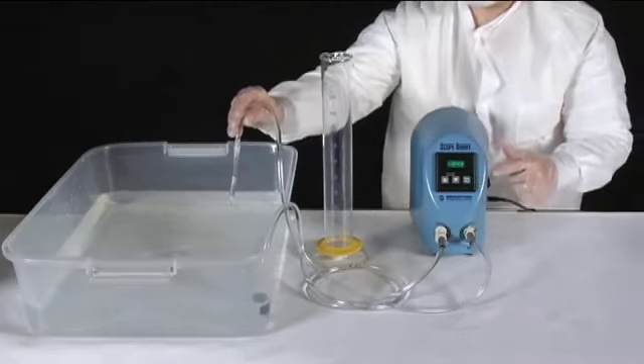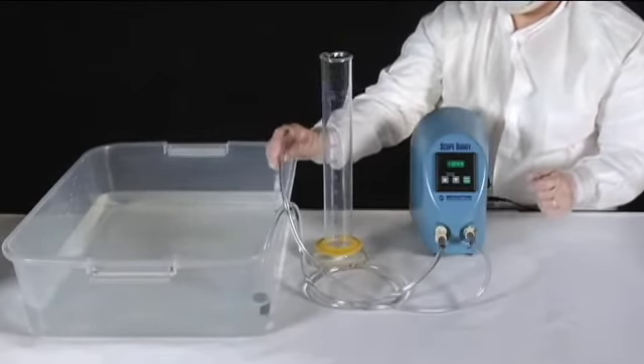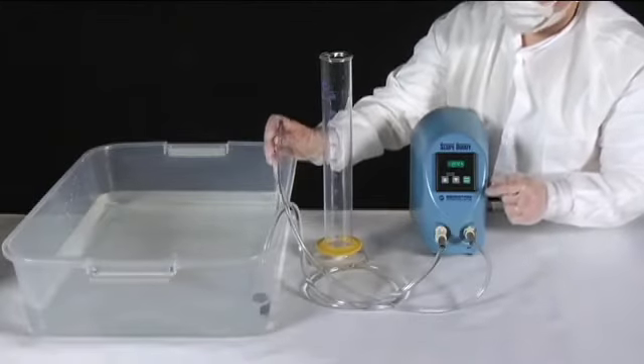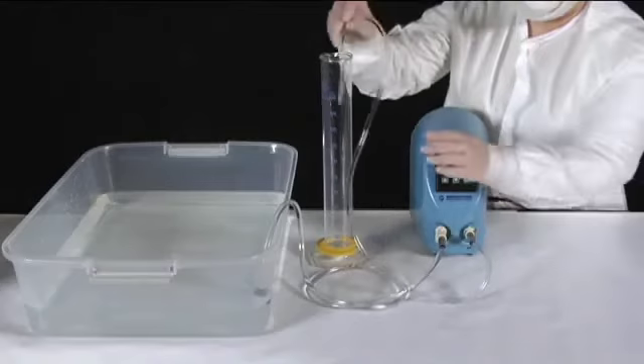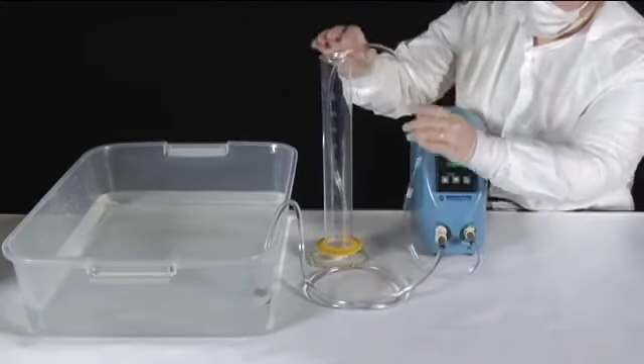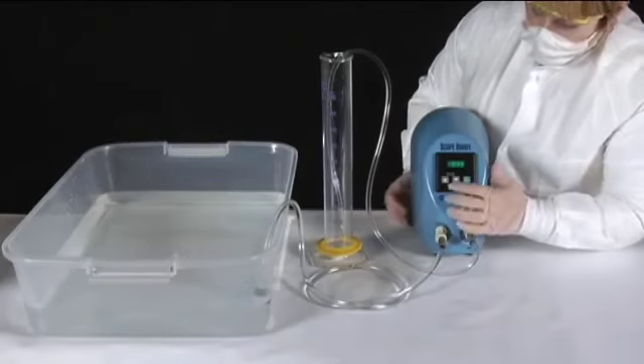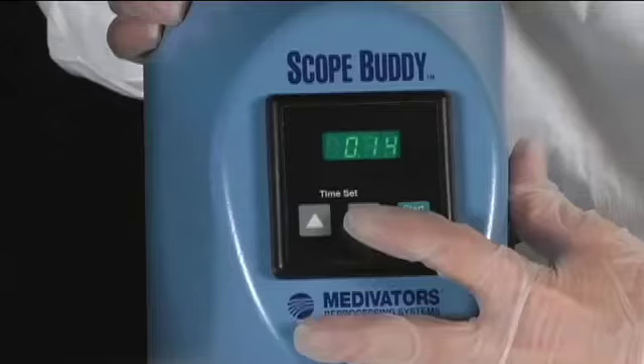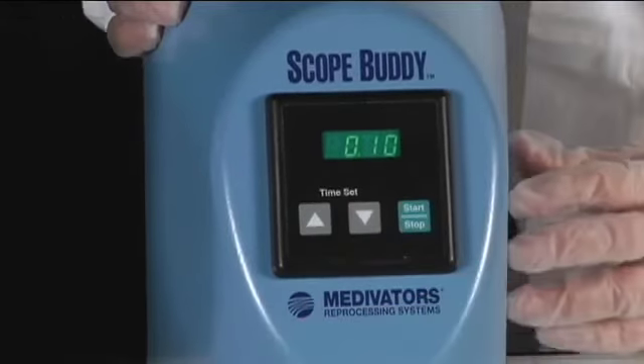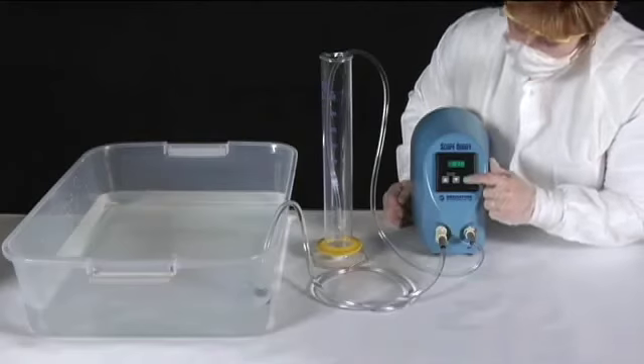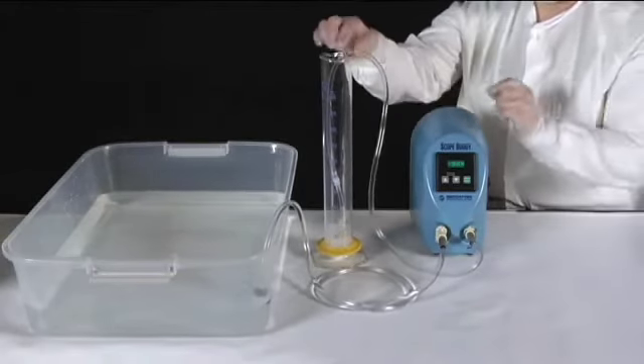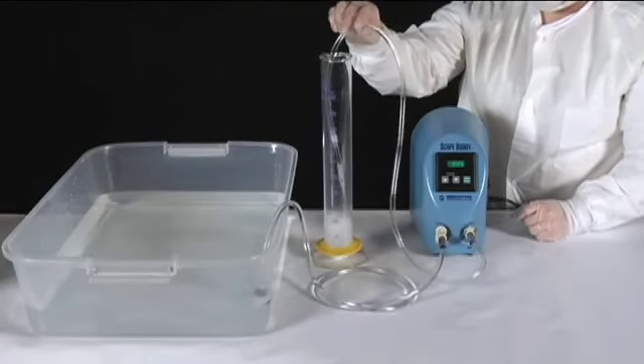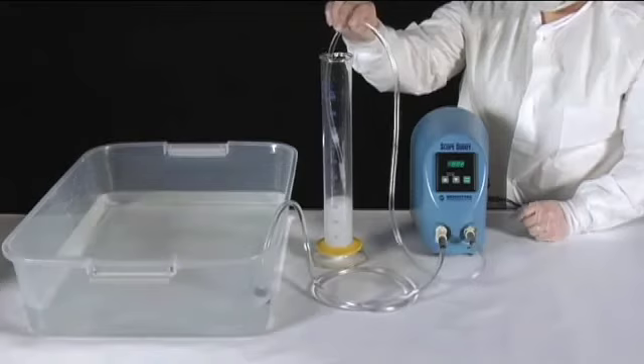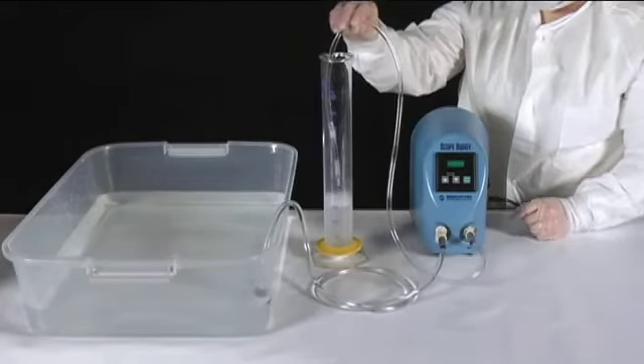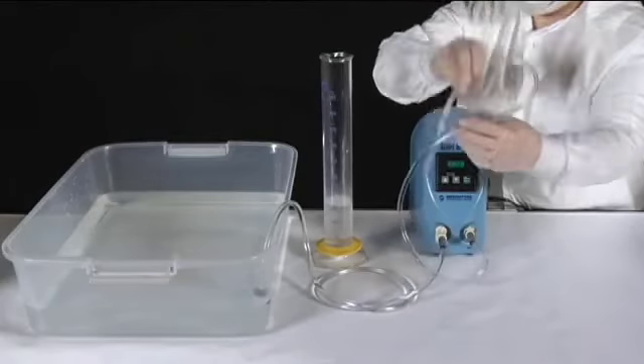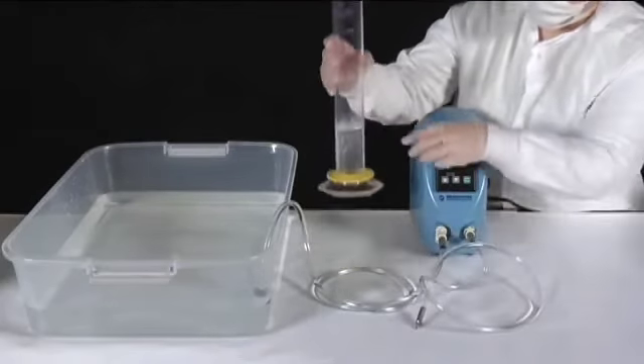To perform the flow verification test, place the open end of the pre-primed flow verification tube into a graduated cylinder or beaker of at least 200 milliliters volume. Using the Scope Buddy front panel arrow keys, set the time display to 10 seconds. Press the Start-Stop button to begin the test. Water will be drawn up from the sink or basin, pumped through the device and into the cylinder or beaker. When the timer counts down to 0, remove the flow verification tube from the graduated cylinder or beaker. Read the volume of fluid dispensed into the container. The volume should be at least 100 milliliters.